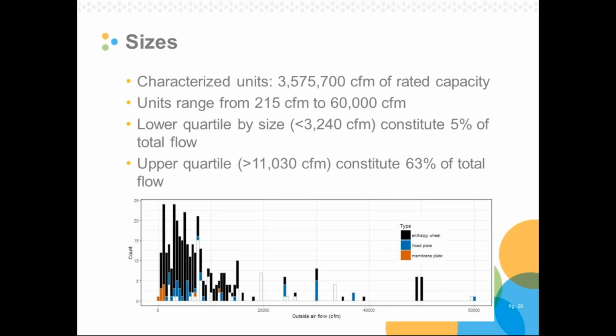This is an important fact. It suggests that if we're looking at a portfolio of energy recovery in the state, it's the big units that matter, the units that are over 10,000 CFM. In fact, they're about 10 times more important than the small units on a total flow basis.